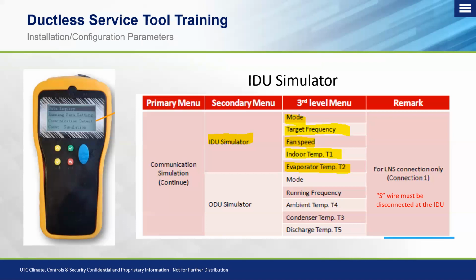But this is certainly great to have for a ducted, floor console or cassette style unit to get that accurate information. Okay, but these are some of the features that we can get in there and simulate and test fire to see if a fan motor is responding or to see if a temperature sensor is reading properly within the range that it should be. And just as a reminder, they read out the temperature sensors in degrees Celsius. We need to convert over to Fahrenheit.